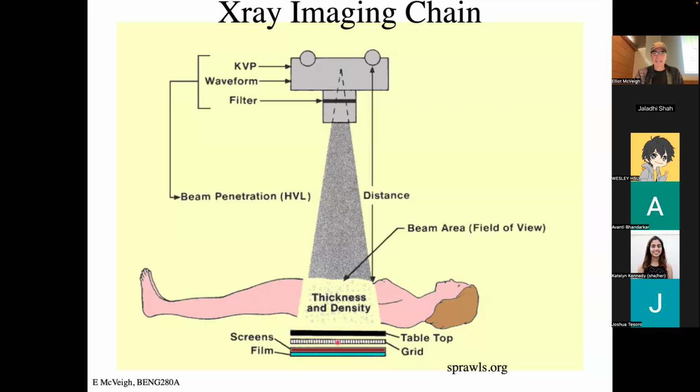This is the anti-scatter grid. If my photon comes through here, has a Compton interaction and shoots off this way, when it hits the anti-scatter grid it will be absorbed. It won't cause a flash down here in my detector. So let's say I survive my travels through the patient and get through the anti-scatter grid, and I hit this, which is a screen.